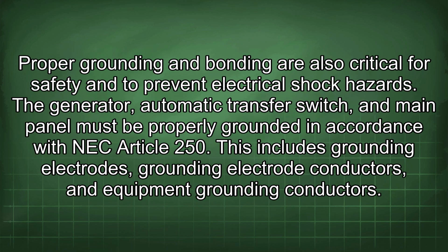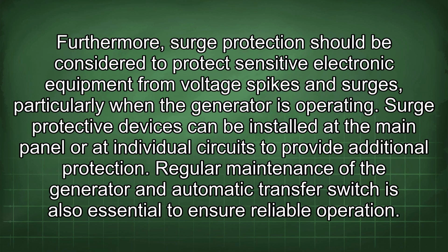Proper grounding and bonding are also critical for safety and to prevent electrical shock hazards. The generator, automatic transfer switch, and main panel must be properly grounded in accordance with NEC Article 250. This includes grounding electrodes, grounding electrode conductors, and equipment grounding conductors. Furthermore, surge protection should be considered to protect sensitive electronic equipment from voltage spikes and surges, particularly when the generator is operating. Surge protective devices can be installed at the main panel or at individual circuits to provide additional protection.